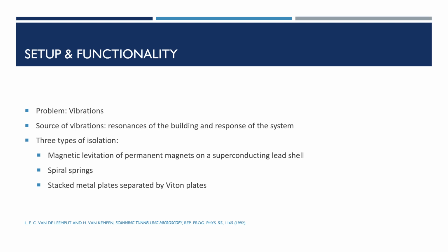The simplest solution is to place the STM in a quiet part of the laboratory and measure at quiet times. This is even more effective if the STM is operating in a medium that carries sound waves. But a better way to reduce external vibration sources is to install a vibration isolation mechanism. There are 3 types of isolation which were used for the STM. The first STM used magnetic levitation of permanent magnets on a superconducting lead shell, but this method is no longer used today. Another method was to suspend the STM with spiral springs.